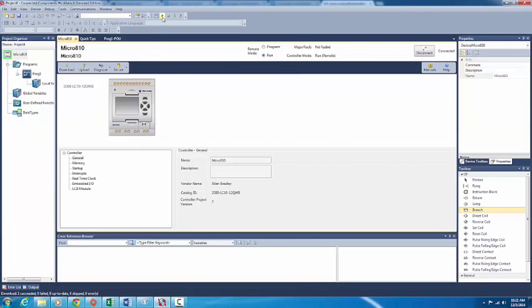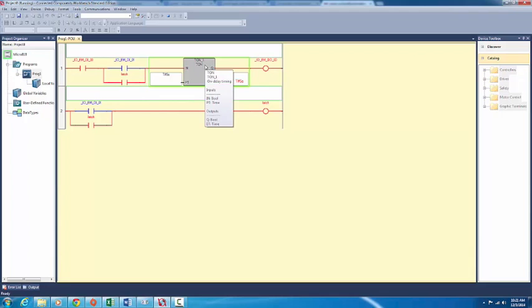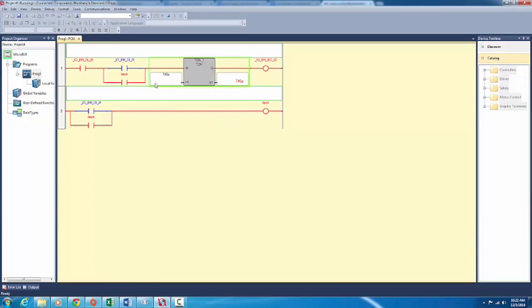Debugging mode — now it's definitely going to work. It's going through the closed switch. Press this — it latches. It starts to count up: two seconds, three seconds, four seconds — and yes, we have an output turning on. That's how we use a timer. That's the TON timer — the on-delay timer. You get power to it, it waits for the elapsed time to reach the preset time, and then it turns on its output.